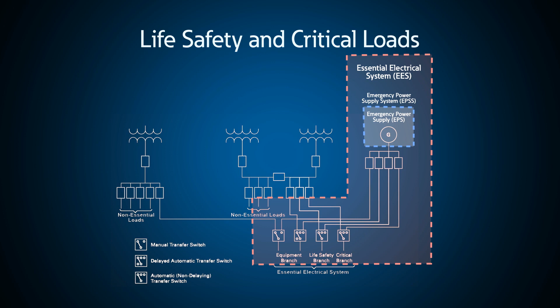It spans 3 branches within the essential electrical system and describes equipment for which standby power must be provided as follows. 1, the equipment branch, which is broken into equipment with automatic connections or automatic or manual connections. 2, the critical branch primarily includes task lighting, select receptacles, and select power circuits needed for effective facility operation. 3, the life safety branch is generally given the highest priority.